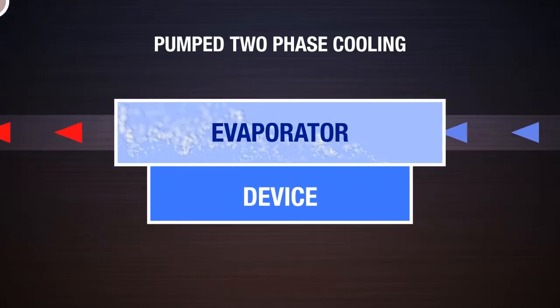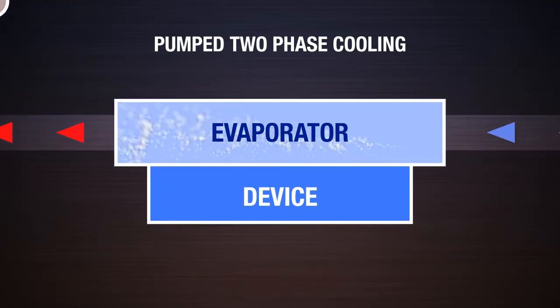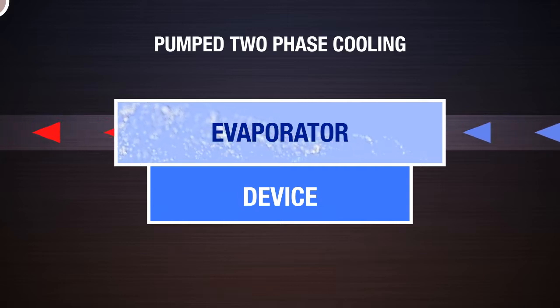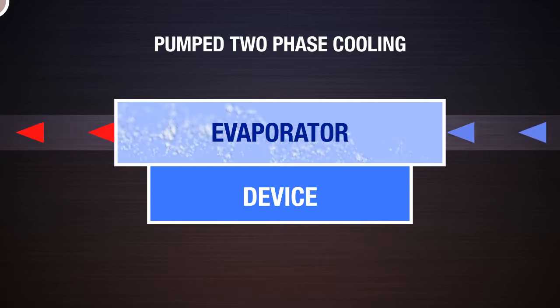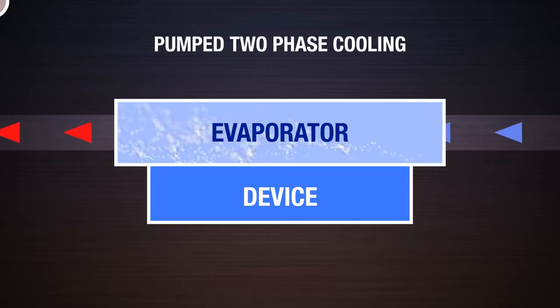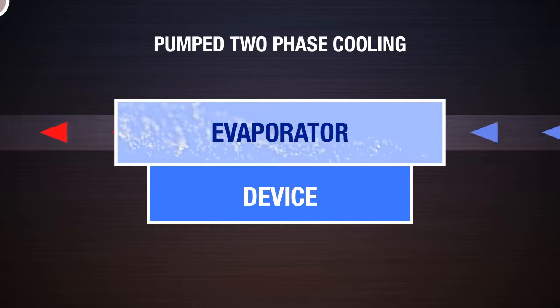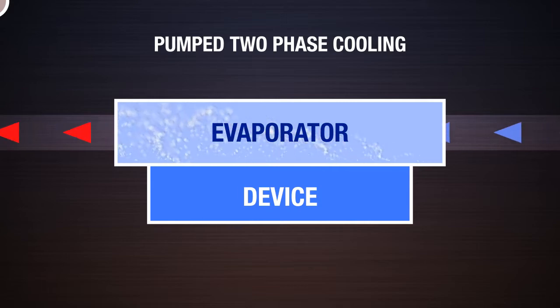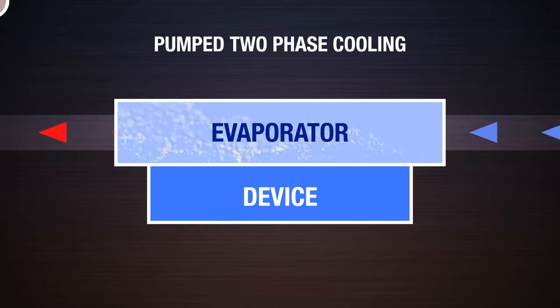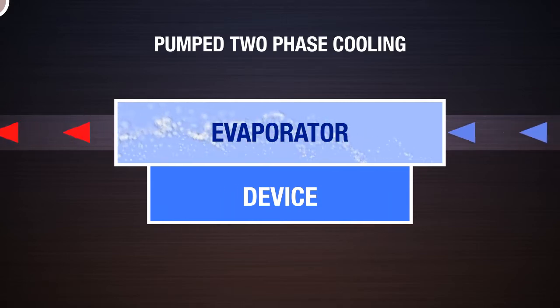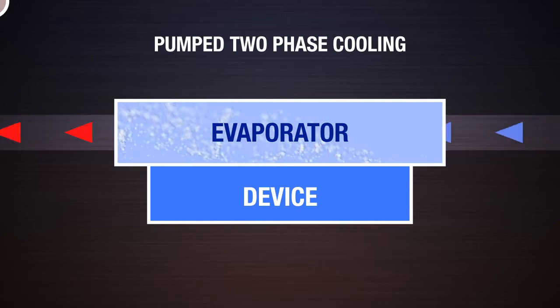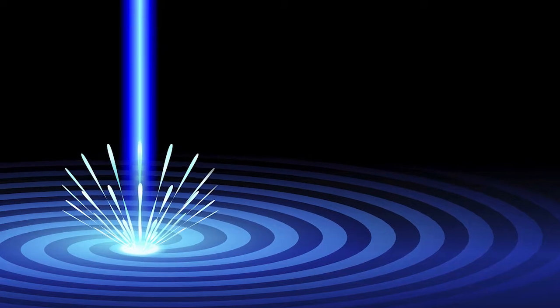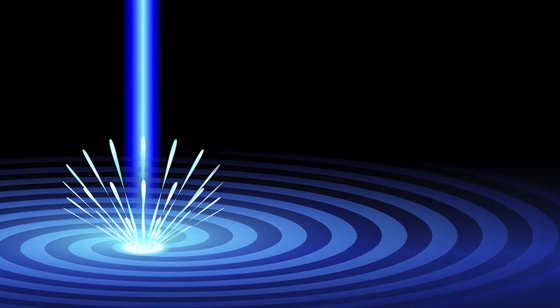Boiling across the entire evaporator surface offers a further advantage in that the evaporator will have a very uniform surface temperature, typically within a few degrees. This near-isothermal performance is important for many applications, such as laser devices, which have wavelength emission sensitivity.